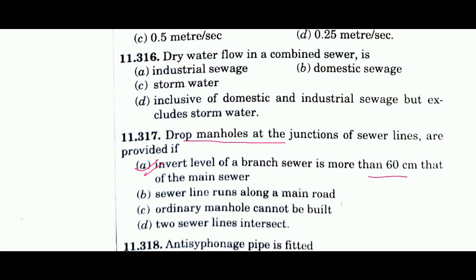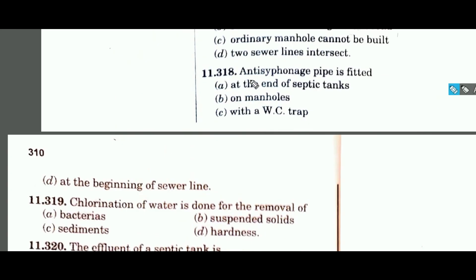Question 318 asks where an anti-siphonage pipe is fitted. It is fitted with the WC trap, so the answer is option C. In a multi-story building, when water is flushed from upper floors, the fast-flowing water creates a vacuum in lateral pipes, breaking the water seal of the WC trap. The anti-siphonage pipe is provided to prevent this.